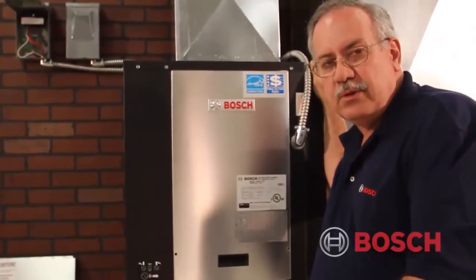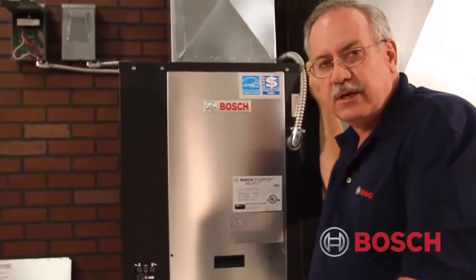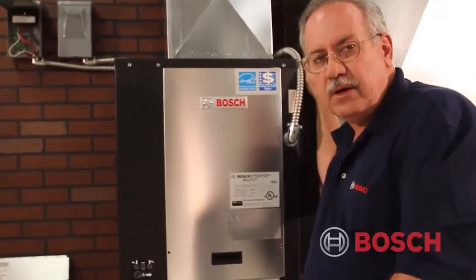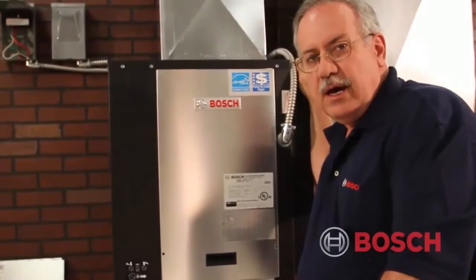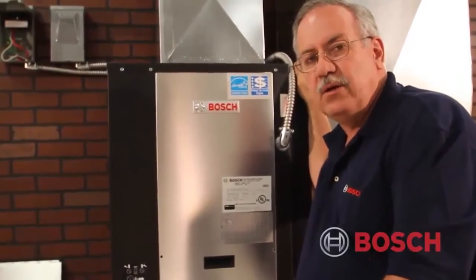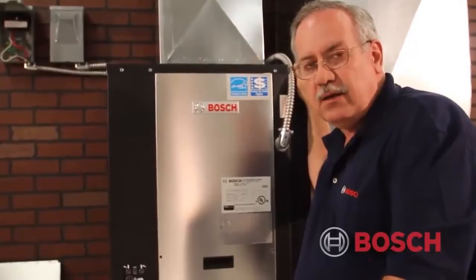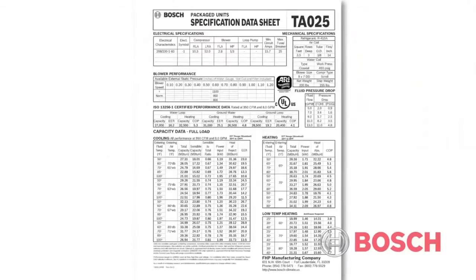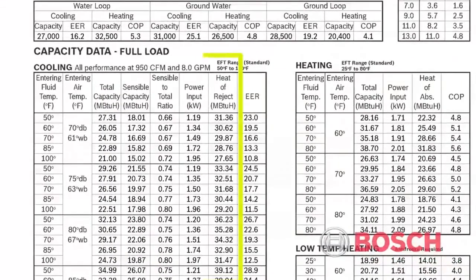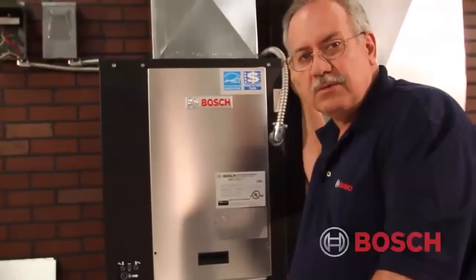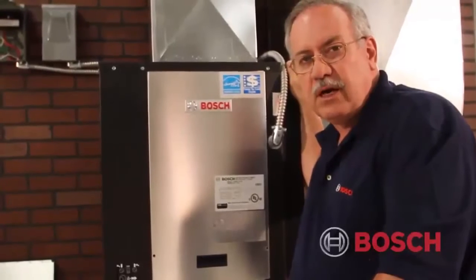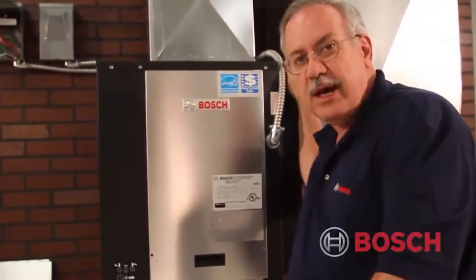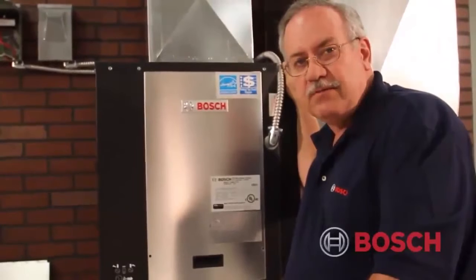So in this particular case, what we'll do is set up all of our components and testing equipment, and we'll refer back to the product literature for this particular unit, and then we'll energize it, in this particular case, in the cooling cycle. Now, if I'm checking in the cooling cycle, I will be determining what we refer to as heat of rejection. That is the heat that is absorbed from the airflow into the refrigerant, transferred into the fluid. If it is an open loop system, this would be only water. If it is a closed loop system, horizontal or vertical, then the fluid would be a combination probably of antifreeze and water. So we'll have some variables involved with that.